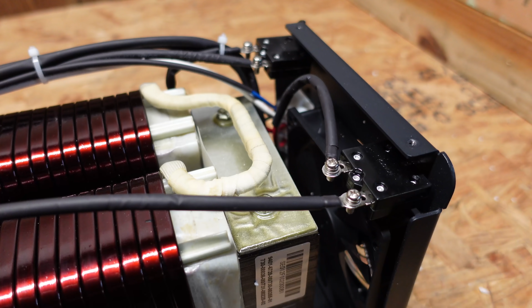So we've also got the main positive and main negative where they enter the inverter. We've got very large bus bars here. On the other side here, we can see each of the output legs goes through these circuit breakers. There's a second one over here before going down to the terminal block. Now, interestingly, the neutral wire coming off of the terminal block is the only one that is a number 10 and is not insulated. All the rest appear to be number 12s.